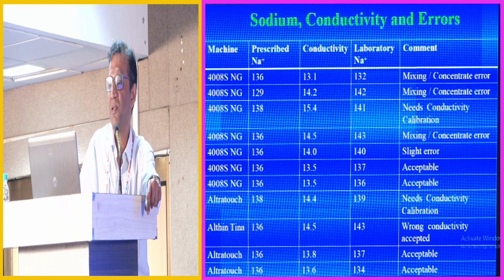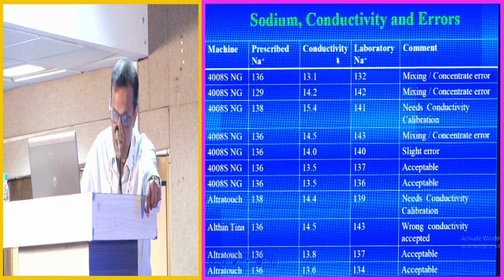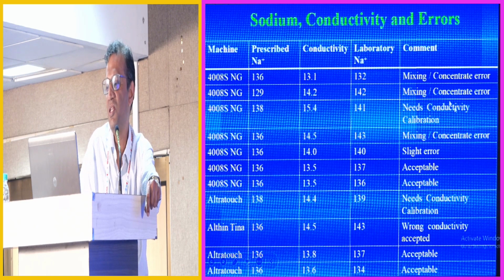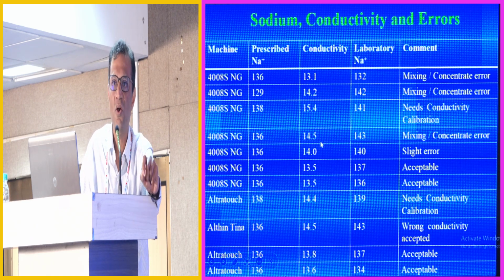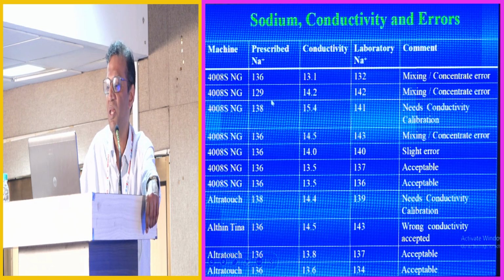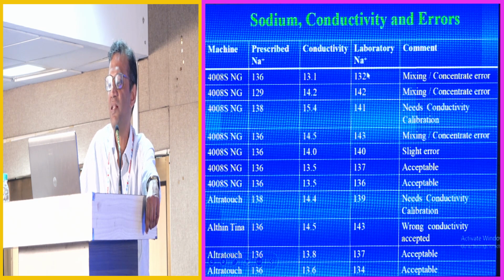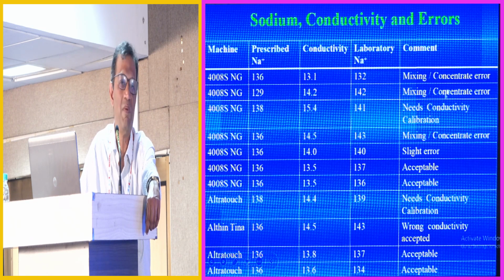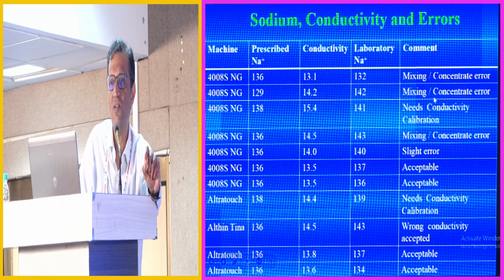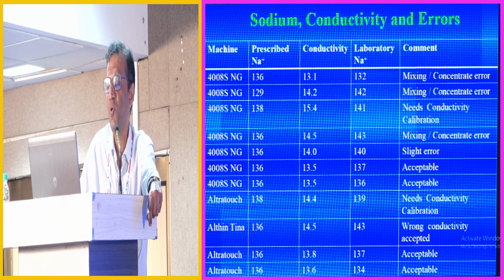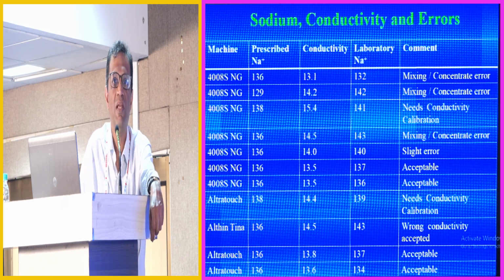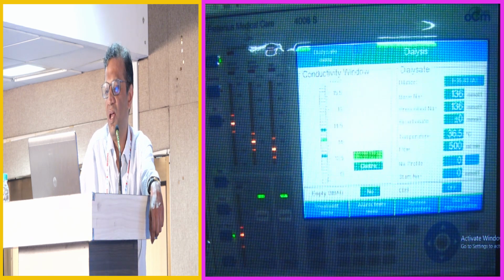Why does this happen? So there could be either an over-diluted or an under-diluted concentrate prepared at the time of mixing, or there could be an error in the concentrate pumps, which will need to be recalibrated. When we looked at what happens in the lab, the electrolytes will correspond not to the prescribed sodium that we have set on the machine, but to the conductivity display, and therefore we take conductivity rather than the prescribed sodium as being the actual sodium that the dialysate contains.